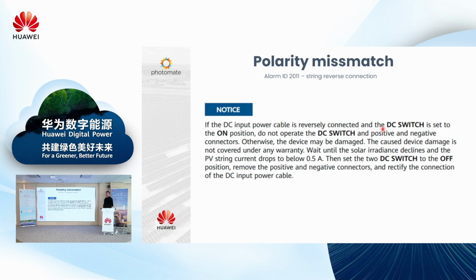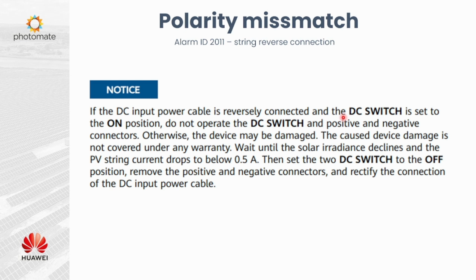If you just read carefully the manual of the inverter, which you won't do, I can guess, like nobody is doing this nowadays, you will find out this information in a short brief. If you have a polarity mismatch on your PV modules, on the PV strings, you mustn't disconnect until the current is less than 0.5 amps. So just put a clamp meter on the DC side and patiently wait until it happens. It might take a while, several hours for sure. So I will tell you how it might end if you want to do it like this, okay?